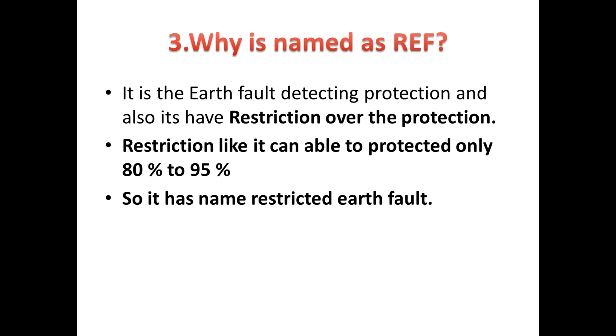Now we go for the third question: why is it named as REF? It is an earth fault detecting protection and it also has a restriction. If we look deeply at this restriction point, it can only protect 80 to 95% of the winding. It has some restriction, and due to this it is named Restricted Earth Fault protection.